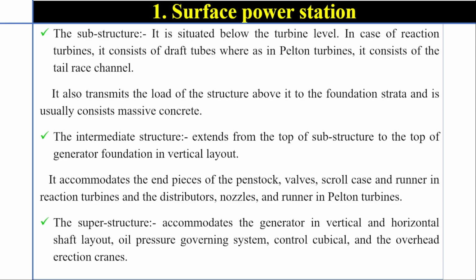The intermediate structure extends from the top of the substructure to the top of the generator foundation in vertical layouts. It accommodates the end pieces of the penstock, valves, scroll case, and runner in reaction turbines, and the distributors, nozzles, and runners in Pelton turbines. The superstructure accommodates the generator in vertical and horizontal shaft layouts, the oil pressure governing system, control cubicle, and the overhead cranes.